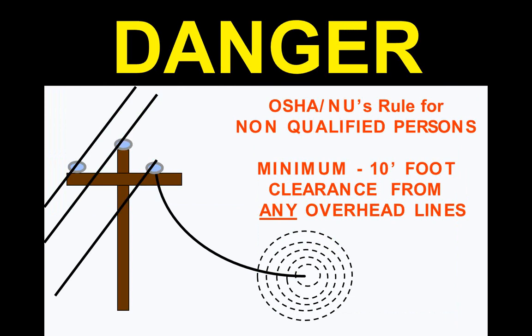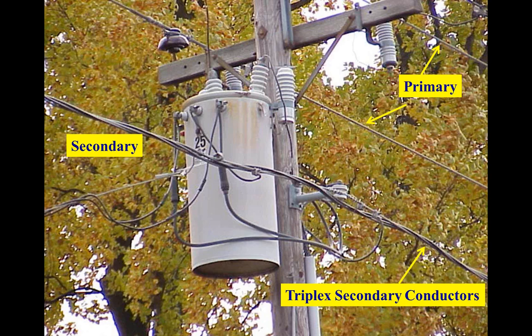And the linemen have a saying: death by primary is going to be closed casket, and death by secondary is going to be open casket. The reason is the amount of damage it's going to do. What do you think kills more first responders and homeowners every year? That 23,000 stuff on top of the pole up in the insulators, or the secondary that comes over and runs to your house? That secondary is what kills more homeowners every year. You have got to respect that secondary as a potential electrical hazard just as much as you do that primary, and probably more. This could be hanging as low as 12 feet off the ground coming over to your house.